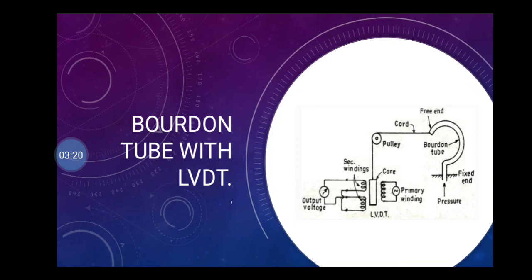What are the disadvantages of the Bourdon tube with LVDT? The first one is that it is affected by vibration. Another one is that a large displacement of the core is needed to get an output. Third one is that temperature affects performance.